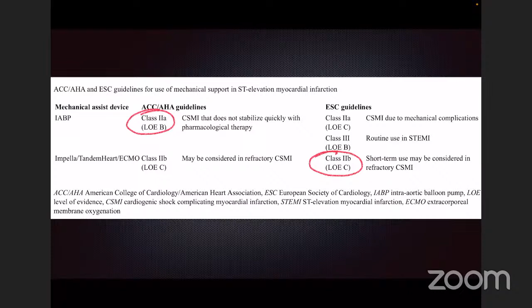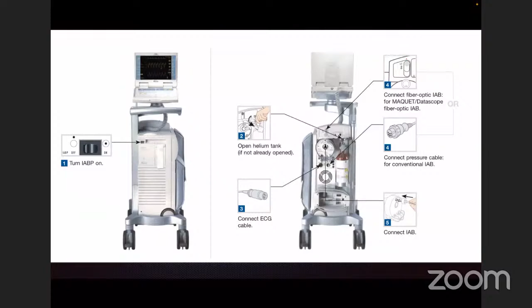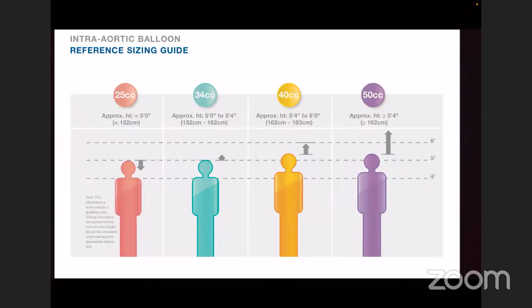So this is basically the console. This is how the back of the console looks. There is a provision for us to open the helium cylinder, a provision to connect the ECG, a provision to connect the helium inlet, and a provision to connect the arterial line. This is just a rough guide for us to know there are different sized balloons available for different people. It's not one size that fits all. Depending on the height of the patient, we can select whichever balloon is appropriate.